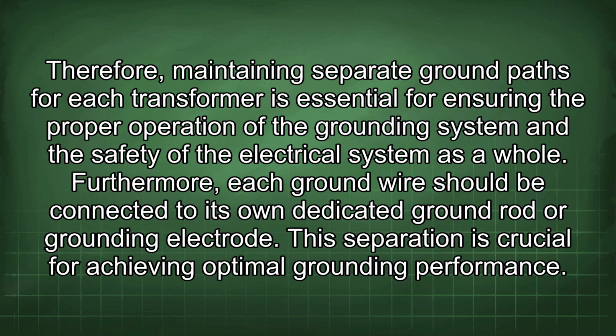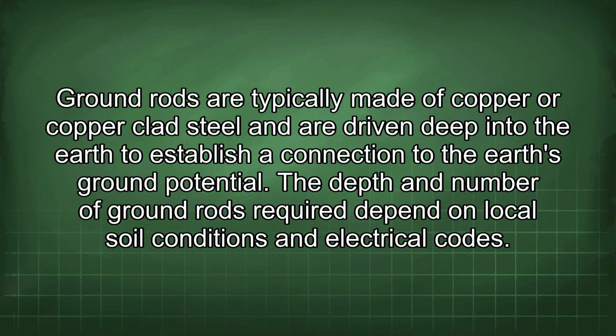Furthermore, each ground wire should be connected to its own dedicated ground rod or grounding electrode. This separation is crucial for achieving optimal grounding performance. Ground rods are typically made of copper or copper-clad steel and are driven deep into the earth to establish a connection to the earth's ground potential. The depth and number of ground rods required depend on local soil conditions and electrical codes.